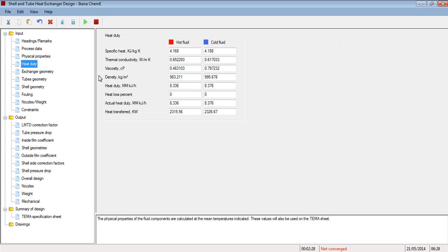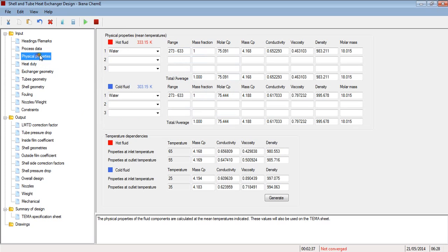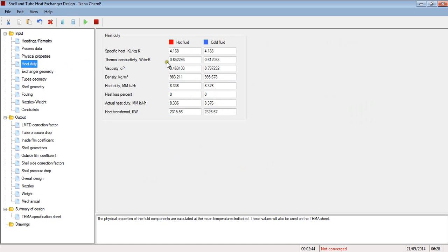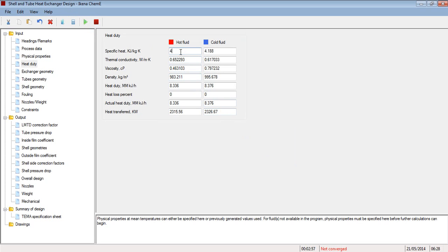Now there are 2 ways of doing this. You can either enter the values here, the specific heat, thermal conductivity, viscosity, densities, or you can use the utility just like we did. If you decide to use the utility, the properties generated here would also populate here, so you don't need to enter them again. But you can obviously go ahead and change them. As you can see, this is a required value, so you'll not be able to proceed without this. So let's just go ahead and enter this value here.